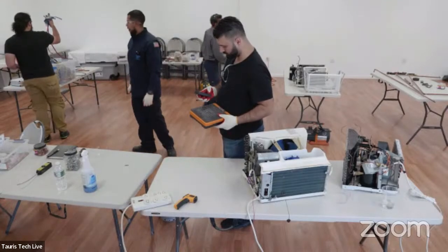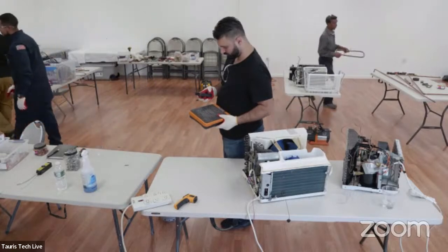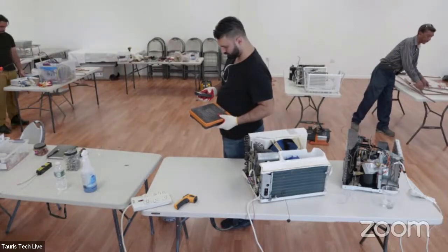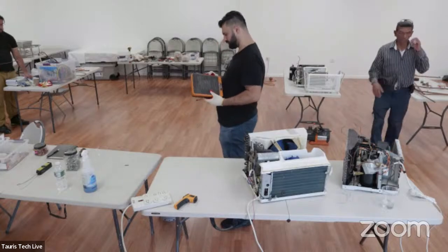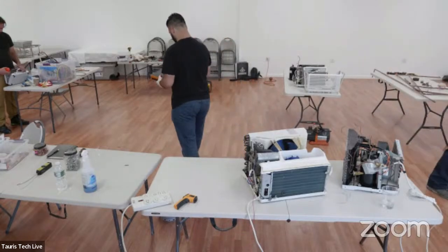You really don't want to mix different refrigerant oils, because if I have a 410A system and I connect to a R22 system, and that oil that's there, funny things start to happen. Okay, that's really what we're trying to avoid.